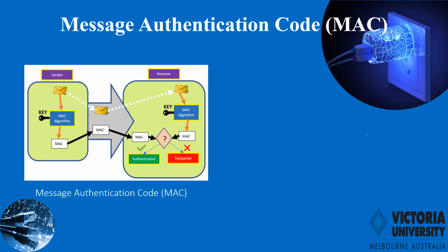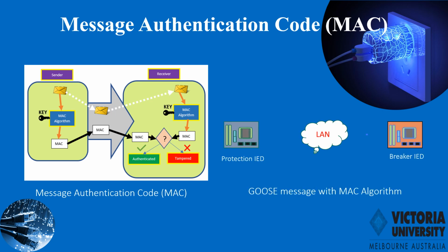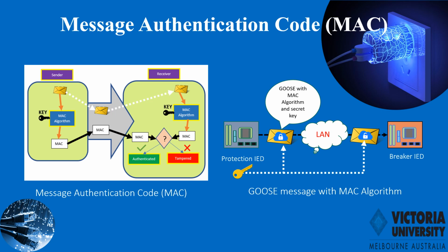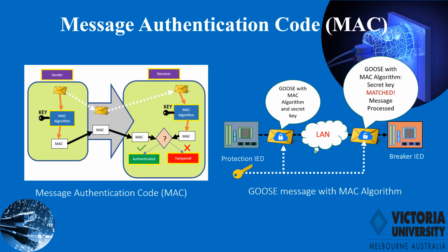This is how a GOOSE message is processed for MAC authentication with a secret key. The sender IED will send a GOOSE message to a MAC algorithm, which will use a secret key. The GOOSE message and the newly generated MAC are sent through an Ethernet link to the IED receiver. The IED receiver will also generate its own MAC with the same key as the IED sender. If the MAC of the receiver is the same as the sender's, the GOOSE message will be processed accordingly. Otherwise, the GOOSE message will appear to have been tampered with during transmission and will be discarded.